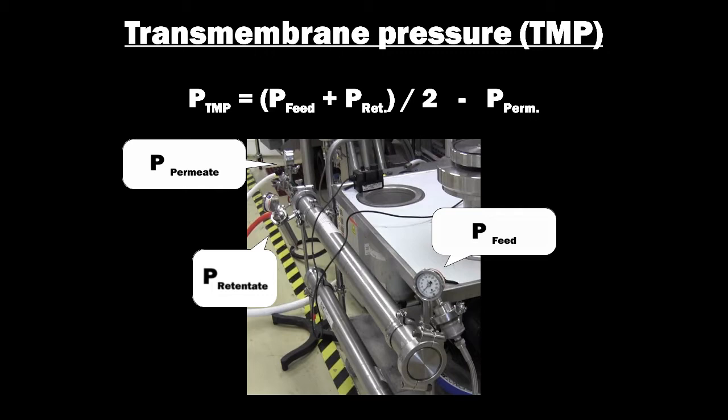When using spiral wound membranes, no back pressure should be applied to the permeate line, and this should remain at atmospheric pressure.